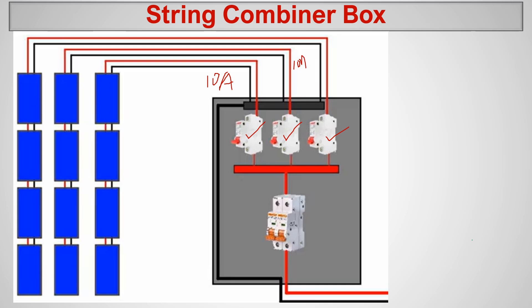Another 10 amperes come from the third string. We have circuit breakers in each string to protect each string — we don't want more than 10 amperes coming from any particular string. Then we have another circuit breaker which combines all three and makes it 30 amperes total. This 30-ampere output goes to the inverter.